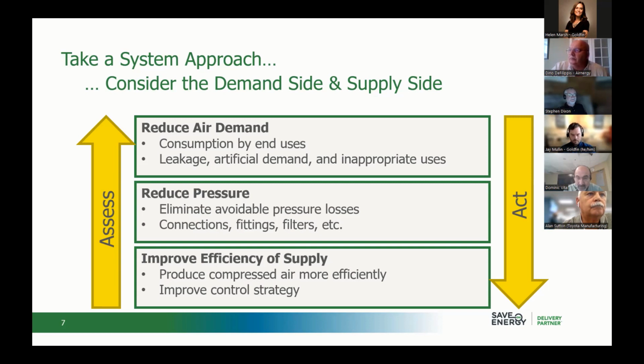And just to define those things, leakage, I think, is pretty simple. Most people know what leakage is, and air that leaks out through either, well, it could be the no-loss valves, right? So when you're on your drain valves, we can have leakage there, or it could be just through leaks in pipe. Artificial demand is where your pressure is unnecessarily high, and then even leaks and inappropriate uses are higher at that higher pressure. So artificial demand caused by artificially high pressure or inappropriately high pressure, and then inappropriate uses, like we all know the classic one, which is sweeping the floor with the compressed air.